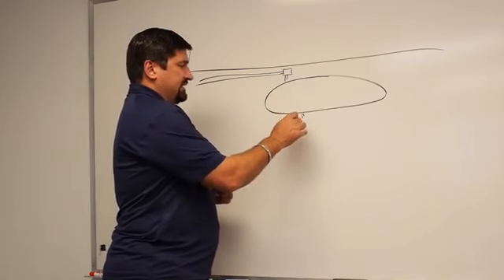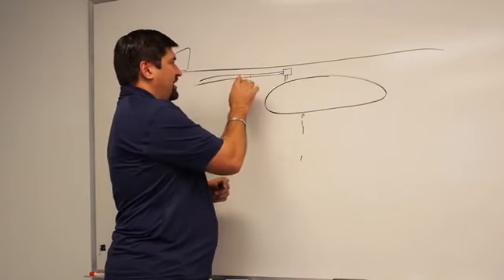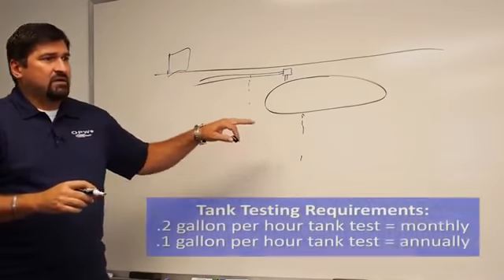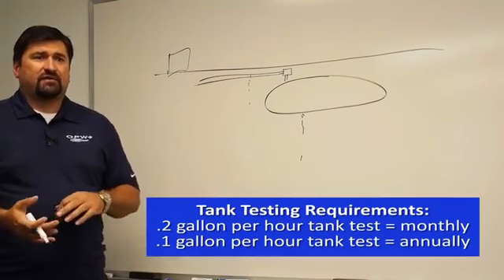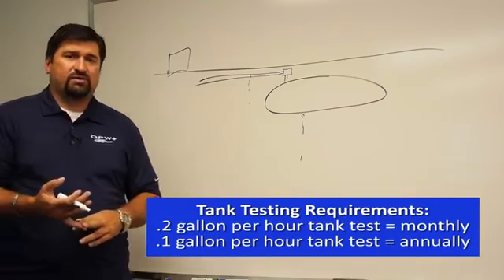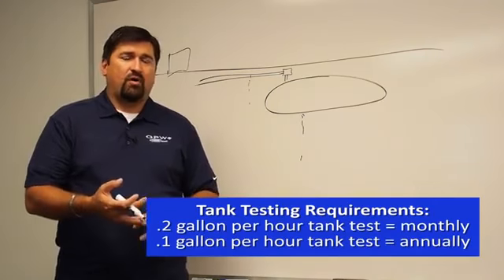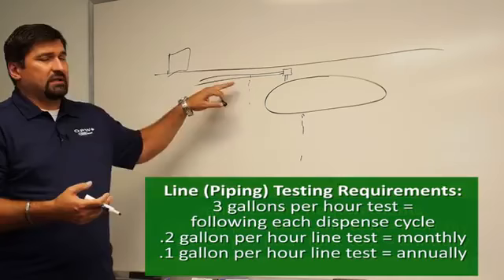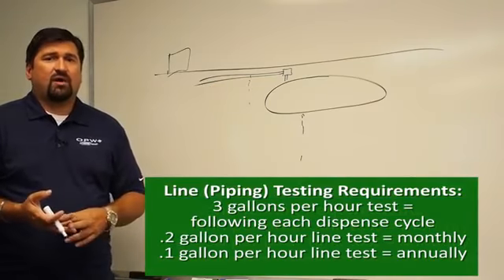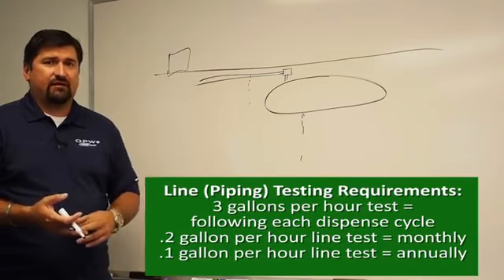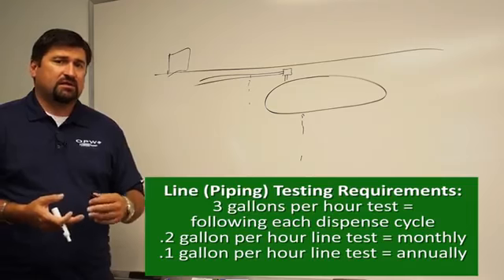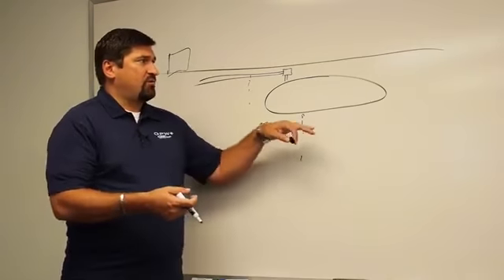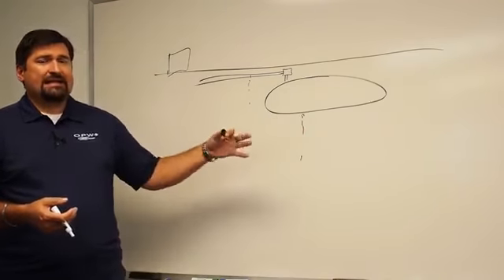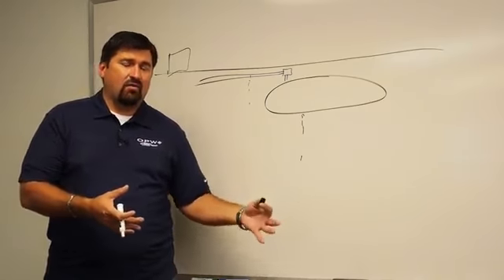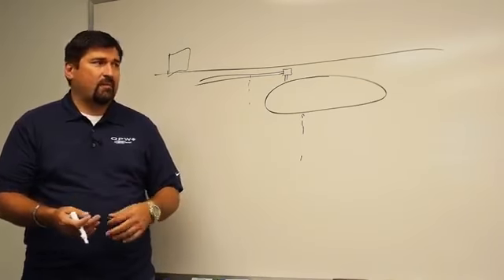Well, let's say you have a tank that's just leaking into the ground, or you have your product pipe that's leaking into the ground. There are federal mandates that you have to do a tank tightness test, either a 0.2 every month or a 0.1 every year. Same thing with the lines. 3 gallon per hour line test after every dispense, and a 0.2 monthly and a 0.1 annually. So most people will install an automatic tank gauge to meet state and local regulatory requirements.